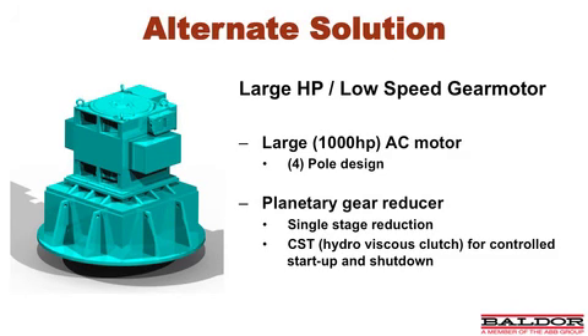So our solution to this particular application is a large horsepower, low-speed gear motor. Large meaning 1,000 horsepower and above, utilizing an AC 4-pole induction motor, as well as a planetary gearbox comprised of a single-stage reduction with a hydroviscous clutch for a controlled startup and shutdown.